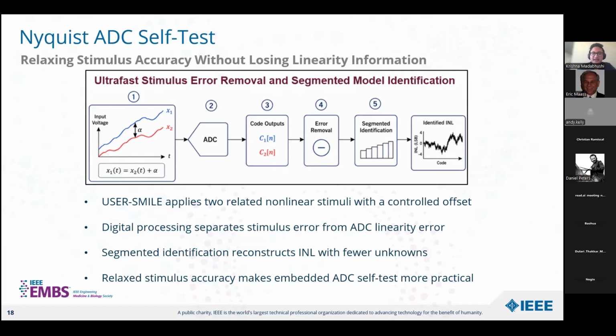This slide is showing one of the principles that's published and is very useful. It's called a USER-SMILE approach. Here we take a different approach. Instead of requiring one nearly perfect stimulus, the ADC is tested with two nonlinear but related signals that have a controlled offset. The ADC converts both these signals, and the two digital data sets are processed together. Because the relationship between the stimuli is known, the algorithm can separate much of the stimulus error from the converter's own linearity error. The important point is that the analog stimulus does not always need to be more accurate than the converter if its error can be identified and removed digitally.